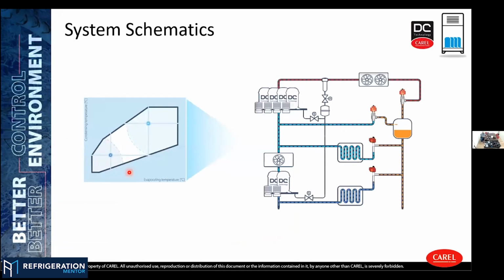And here is an example. All the time, both compressors are running and adjusting. As you can see, we are out of the envelope and the unit is trying to correct and push it back into the application. All the time we are looking at the compressor safety and trying to make sure that the compressor is running in proper condition. This is built in and developed by us. It's not something that you need to develop by yourself. It's pre-built into our applications.